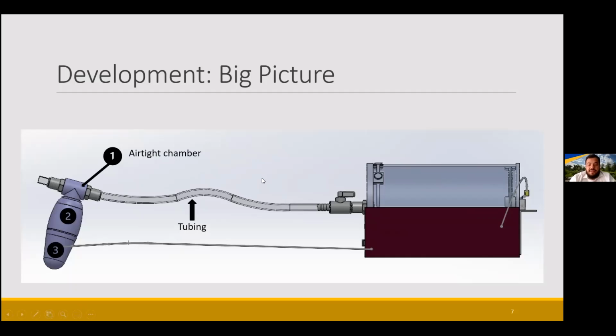As we head over to the volumetric cylinder, we run into a shutoff valve. Now, this is important because, as I mentioned, the first chamber needs to be airtight, and we know for a fact that our volumetric cylinder isn't airtight. So we need to be able to cut off access to the leakiness of the volumetric cylinder once our patient is done taking a breath.